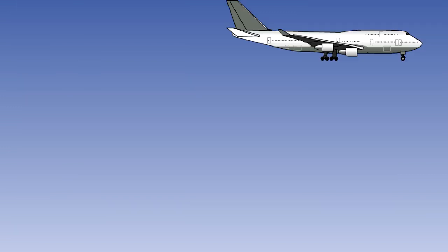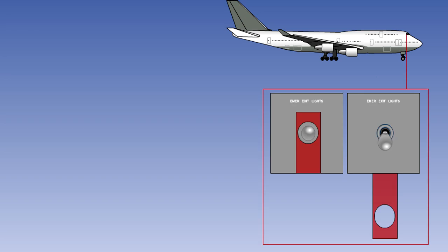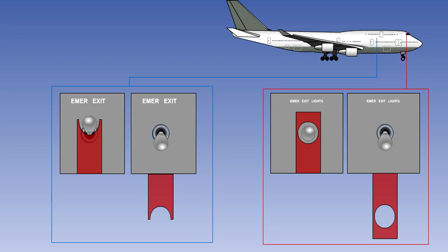The emergency lighting system is controlled by two switches: one on the flight deck and the other in the passenger cabin adjacent to a cabin crew member station. The flight deck switch has three positions: off, armed, and on. It is guarded to the armed position and is in the guarded arm position for all normal flight operations. Adjacent to the flight deck switch, there is a warning light captioned 'not armed'. This light is supplied from the normal aircraft electrical power supply and will come on at any time the aircraft electrical power supply is on and the emergency lights are anything other than armed.